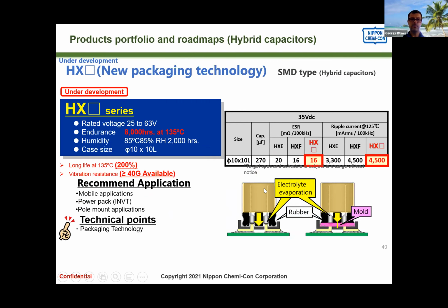One reason is higher, longer life. We mentioned earlier that electrolyte diffuses through the rubber band and is lost a little bit — most of it is consumed, but some is lost through diffusion, especially on thin rubber band designs like surface mount. So anything we can do to control or decrease this electrolyte diffusion results in longer life, and that's essentially what this thin layer of epoxy does — it decreases the evaporation rate and pushes back the end of life.